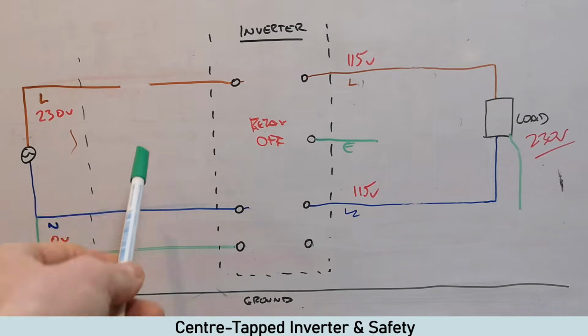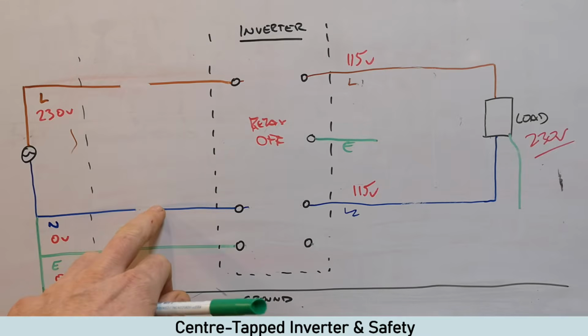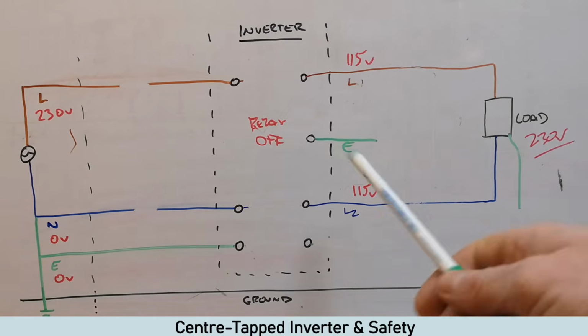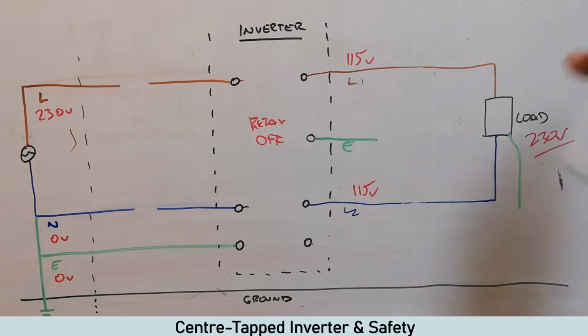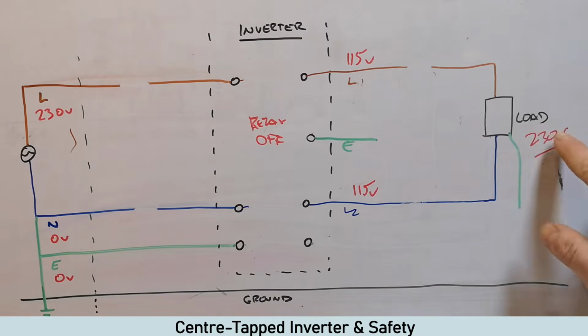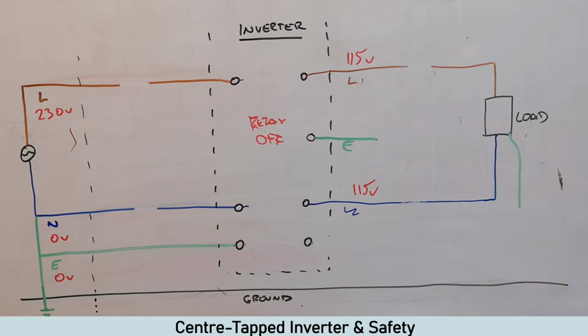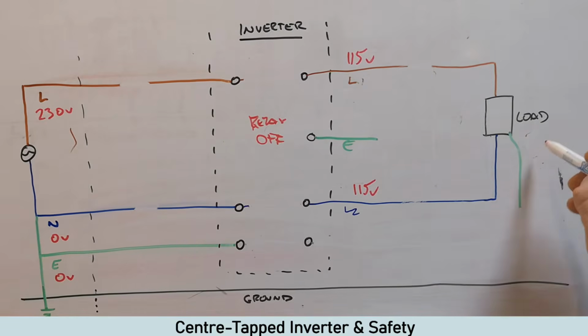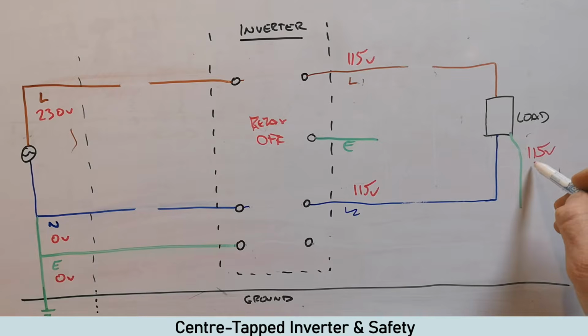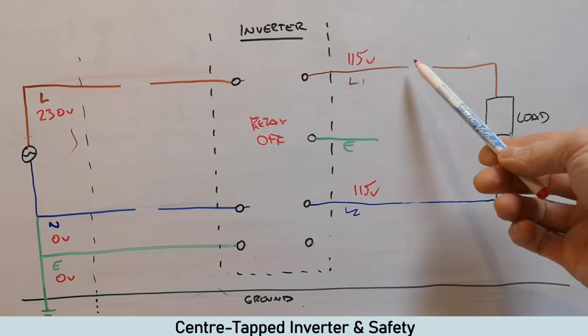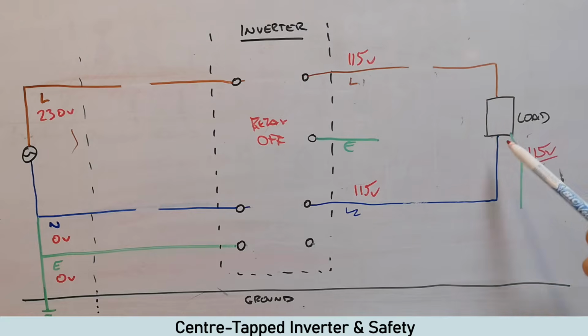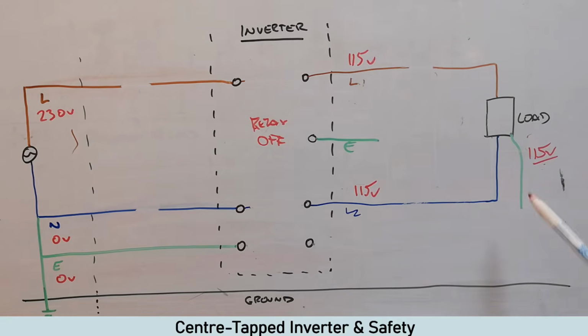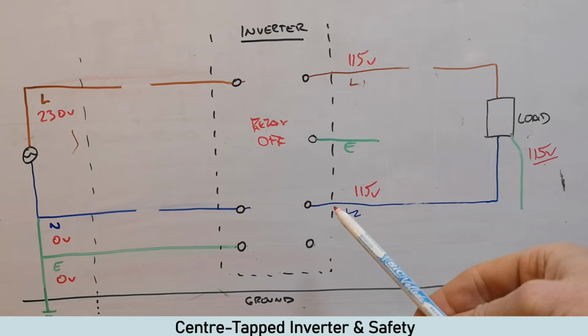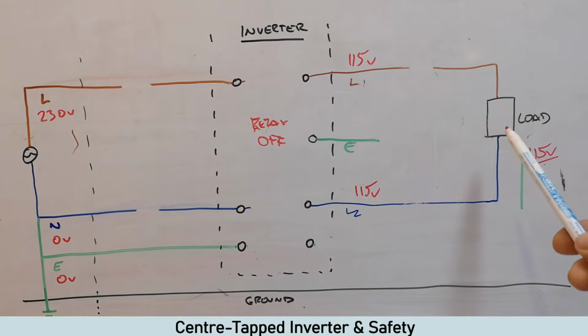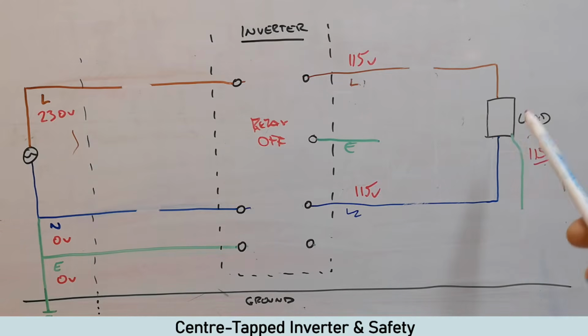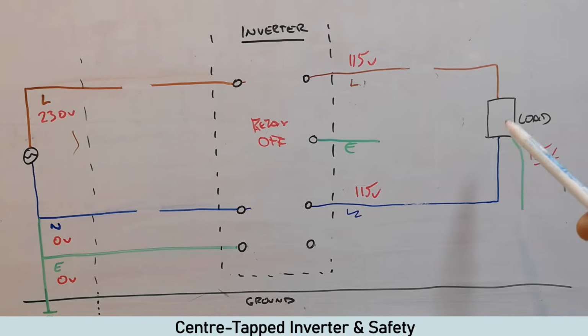So that's single pole. What double pole means is it cuts both the live and the neutral. So on this side, if you disconnect the live there, this will no longer be 230 volts, but you're going to have 115 volts at your load, even though it's turned off. Whereas on this one, you're actually going to be getting 115 volts on line 2, even though it's turned off. So that could cause issues depending on what you're plugging in.